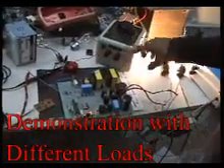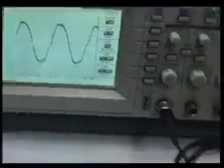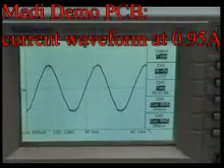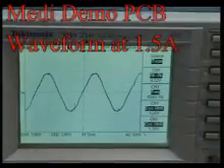Now I am showing the different load power factor. Here the same arrangement — the AC input is connected through the Hall-effect CT, but also an ammeter is connected in series. Now the current waveform is showing at 0.45 Ampere. See this is the current waveform at 0.45 Ampere. Now the current waveform at 0.95 Ampere — see, this is the 0.95 Ampere current waveform, I expanded it. Now at 1.5 Ampere — see that very low harmonic and very high power factor.